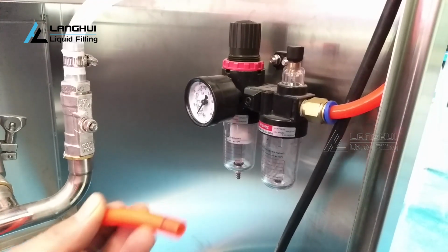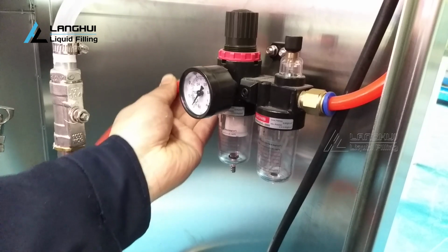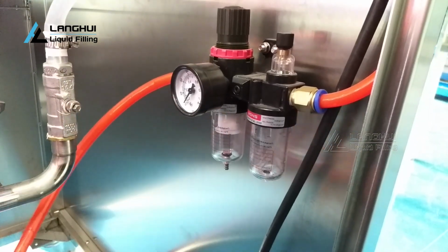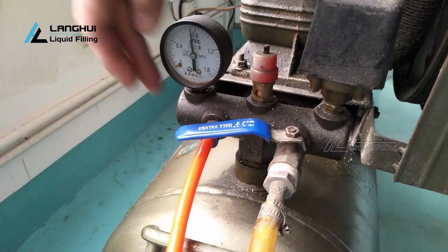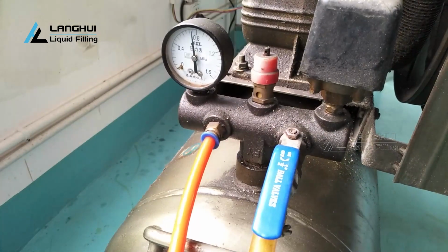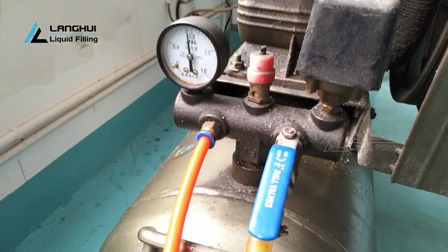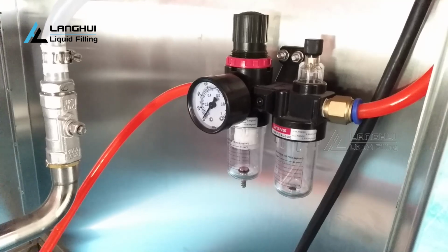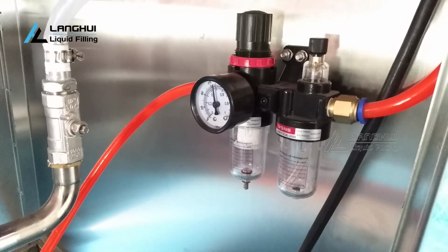Please check the standards of the air supply. Air pressure is 0.6 to 0.8 MPa, and the discharge flow of the air compressor is more than 300 liters per minute. Please connect the diameter 10 mm compressed air pipe to the FRL of the machine and input dry and clean compressed air. You had better add an air storage tank before the air filter. This will make the machine run more smoothly, stably and last longer.